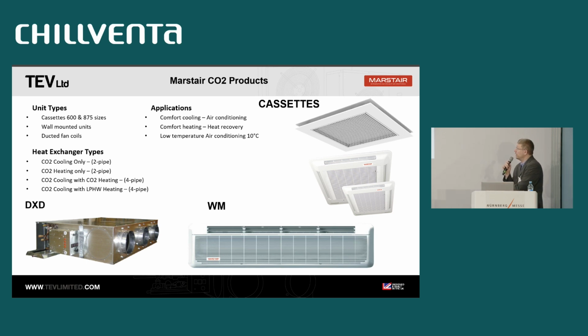We also, and these are probably the most popular, do 4-pipe units. Because within the system, your recovery needs to come from 2 different places within the pack, you tend to have a 4-pipe if you want to do cooling and heating. So you have 2 separate heat exchangers within the cassette or the DXD. That way, through the system, you can decide whether you want to pump hot gas through it when you need heating, or you can do the cooling side and put some of the cold refrigerant through it if you want to do cooling, through 2 completely separate circuits.